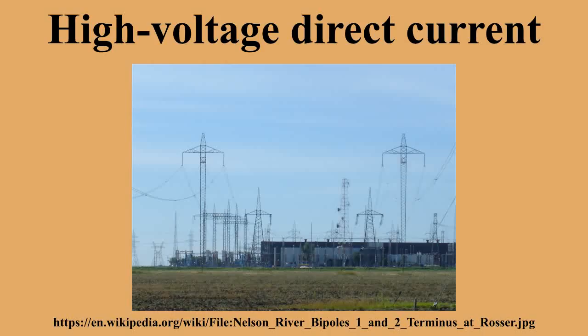Voltage source converters started to appear in HVDC in 1997 with the experimental Hellsjön-Grängesberg project in Sweden. By the end of 2011, this technology had captured a significant proportion of the HVDC market. The development of higher-rated insulated gate bipolar transistors, gate turn-off thyristors and integrated gate-commutated thyristors has made smaller HVDC systems economical. The manufacturer ABB Group calls this concept HVDC Light, while Siemens calls a similar concept HVDC PLUS and Alstom calls the product based upon this technology HVDC MaxSine.